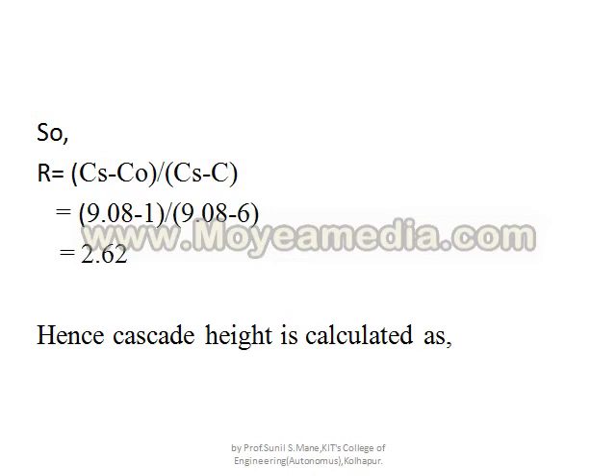Now for the calculation, we first calculate R. The saturated concentration of oxygen is 9.08 mg/L, the initial concentration in the raw water is 1 mg/L, and the required concentration is 6 mg/L. Even if the required value is not explicitly given and the problem asks to design a safe cascade aerator, you should take 6 mg/L or more. Using the formula, R comes out to be 2.62.